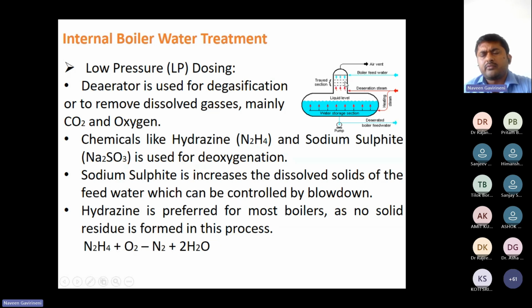treatments: mechanical treatment and chemical treatment. The mechanical arrangement has a tray arrangement. We give steam here, which goes upward. While the feed water comes down, it gets heated up, and any gases are removed through the air vent along with the steam. This is the heating arrangement, and that is the mechanical deaeration. Chemical deaeration is by adding hydrazine.